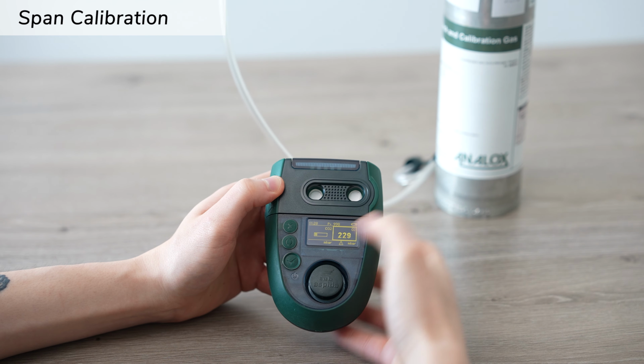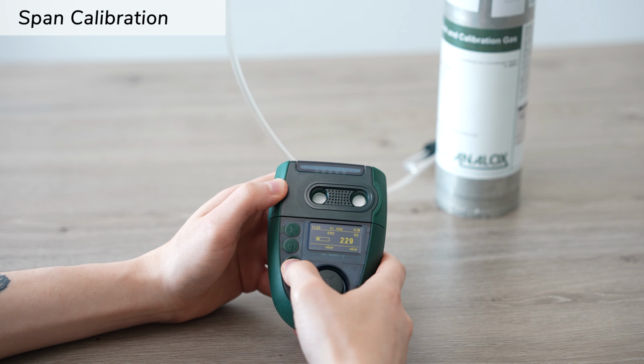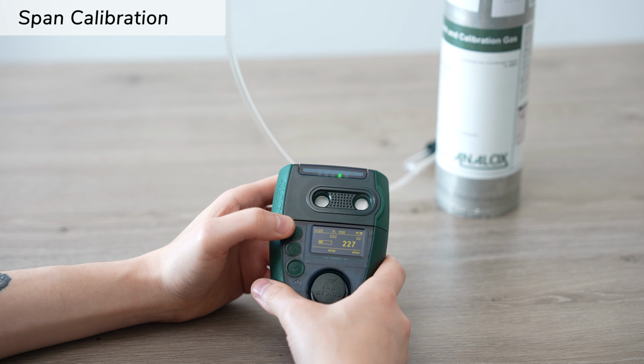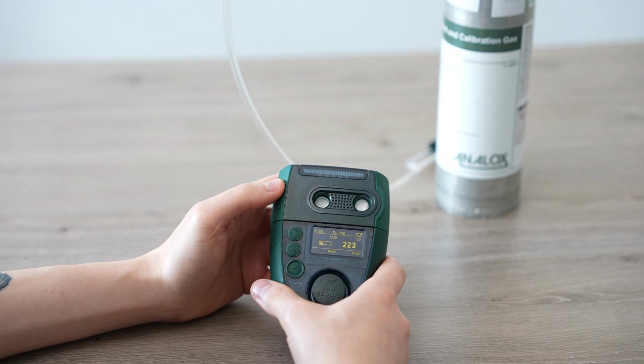The O₂ uses the same process, however, we only have to span calibrate the O₂ sensor. If at any point calibration fails, please check that you are only allowing ½ litre per minute to flow over the sensors and that you are using the correct calibration gas.